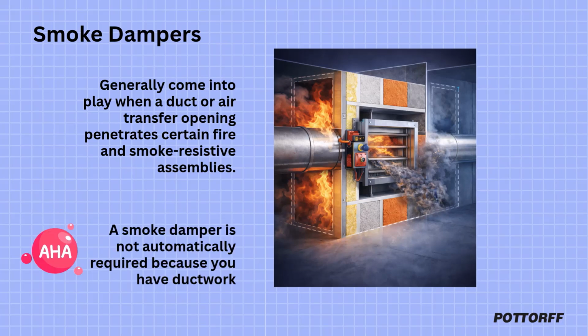And a big aha for new folks, a smoke damper is not automatically required just because you have ductwork. It's typically tied to the type of barrier you're crossing and the building's life safety design, especially in places like healthcare where smoke compartments matter.